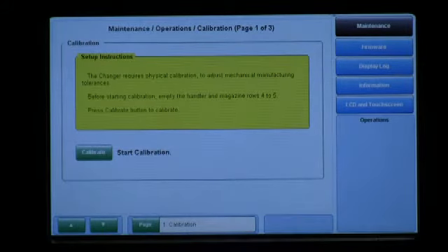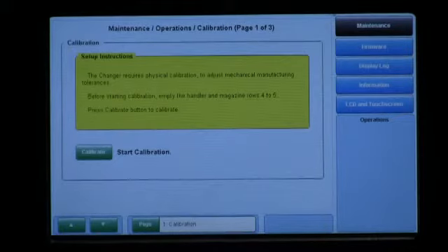proceed with the calibration. For this particular library, it states, before starting calibration, empty the handler and magazine rows 4 to 5. This message is telling you that you will have to remove both the left and right side matrices from the library and remove all of the tapes that are currently situated in rows 4 and 5 of both matrices.